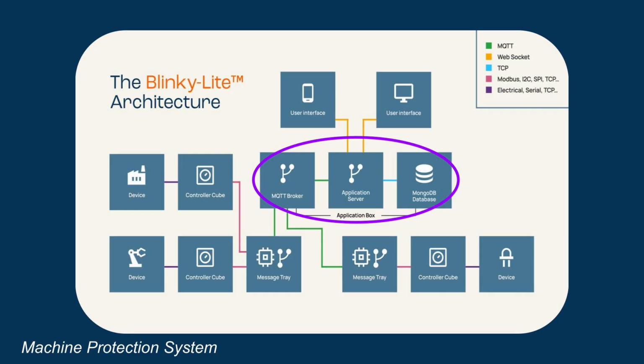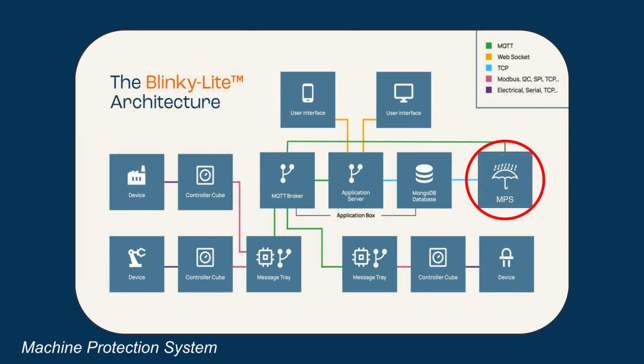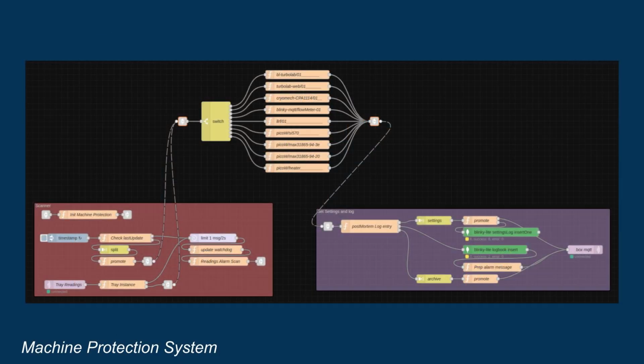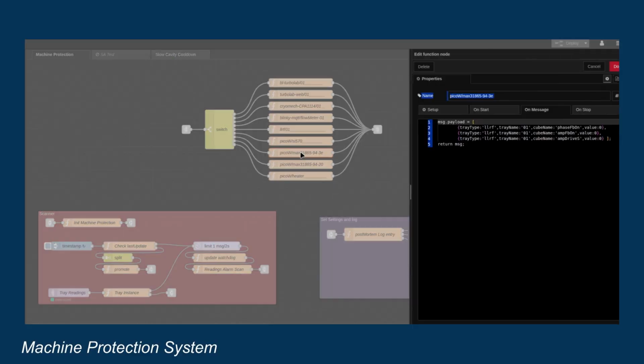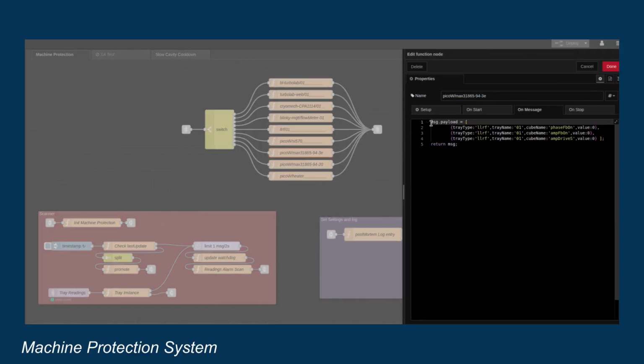The core of the machine protection is a process on the box that listens to this MQTT feed for tray updates. This process scans the trays for alarms. If a tray enters an alarm state, or if the tray hasn't been heard from for a set period, an action switch is notified. The power of this system is that custom actions can be added graphically to this switch.